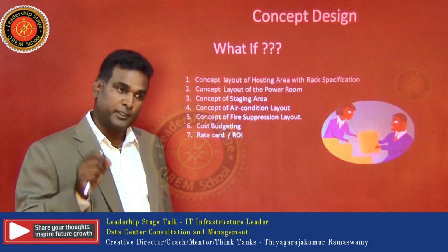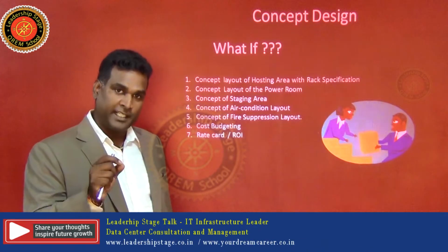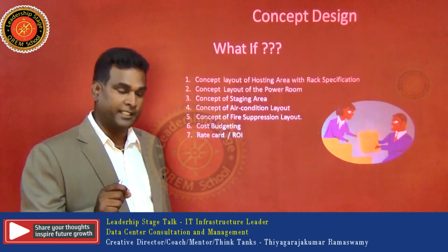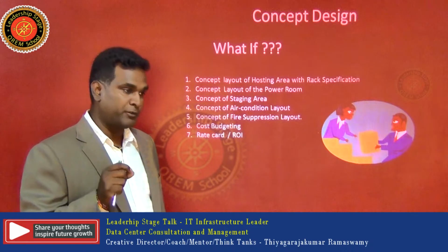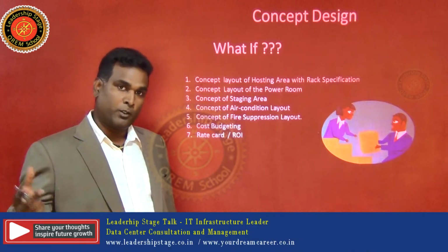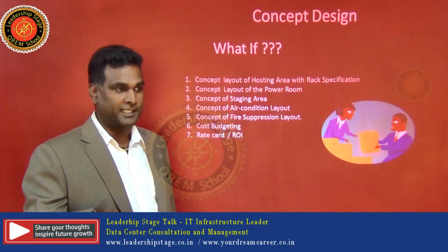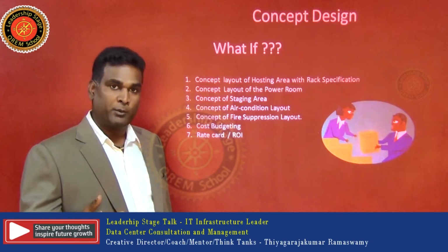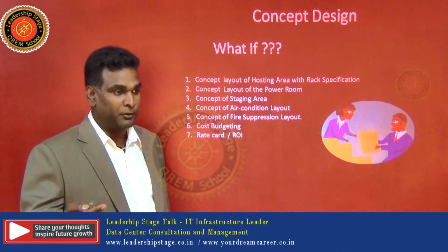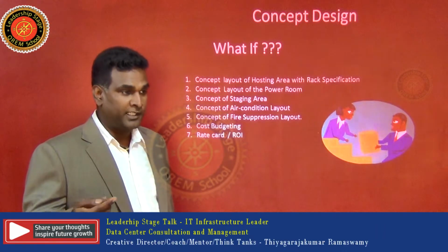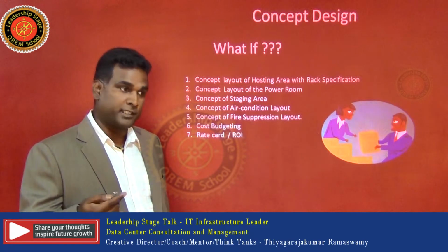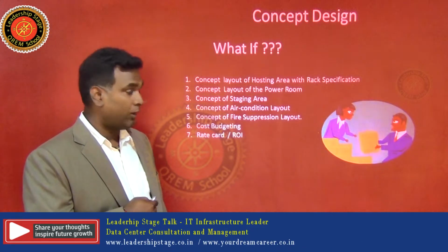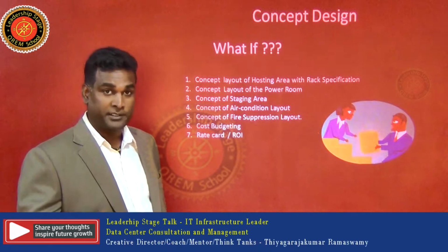So what is important is when you're building a system, or when you design and when you're reviewing the detailed design, ensure it is scalable in nature. That's the key, right? The reason why we talk about a key aspect of scalability is you don't want to put all your $5 million day one, because then you're talking about a huge negative recovery in the first year. So you probably want to take a business assumption that, well, I'm going to fill 20% of my data center year one, and then you probably put in an investment and an infrastructure size of 40%, and then scale up, right? Because you are designing a scalable and concurrent maintenance data center, so you better scale up.